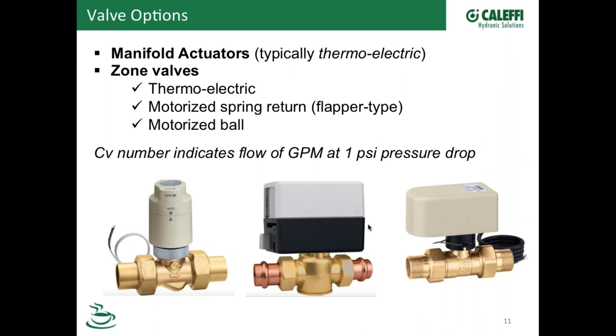So on the left there is what's called a thermoelectric valve. Basically there's a little heat motor in here, and as you apply power to that, that little cartridge gets warm in there and it opens this valve here. It's kind of, I guess we'd call it, a plunger style valve. It just raises and lowers a little flat disc onto a seat in here. What's nice about this type of valve is it's completely quiet. You won't hear any motor, you won't hear any springs, you won't hear any gears or anything like that. That's typically the actuator that you'll see on radiant manifolds, because obviously sometimes those might be in a bedroom wall or closet wall or something like that, and you don't want to hear any sound at all. So that's the beauty of a thermal type of actuator, in my opinion.